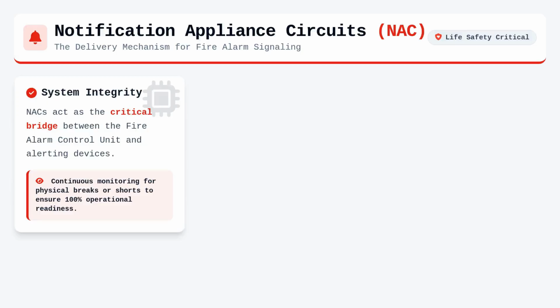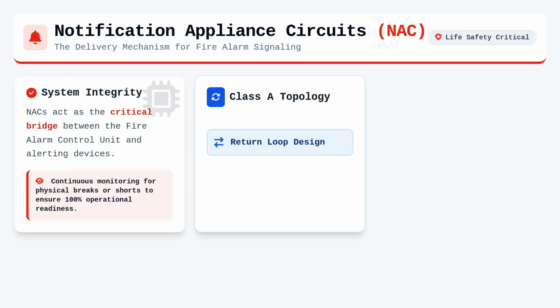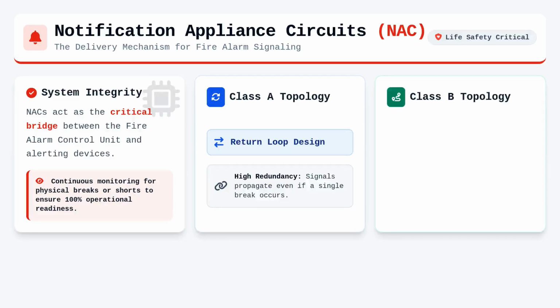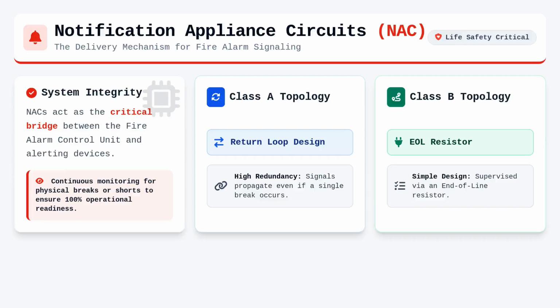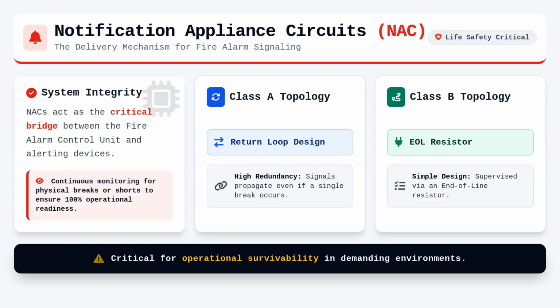When we look at the wiring topologies, we often distinguish between Class A and Class B configurations. Class A circuits utilize a return loop to the control panel, ensuring that even with a single break in the wire, signals can still propagate. Class B circuits are simpler in design, but rely on an end-of-line resistor to maintain constant supervision of the entire circuit length. Understanding the nuances of these configurations is essential for maintaining the operational survivability of fire alarm systems in demanding environments.